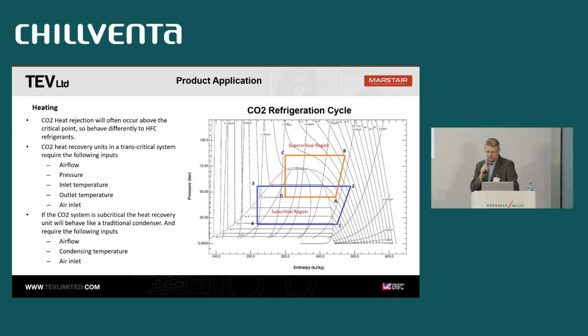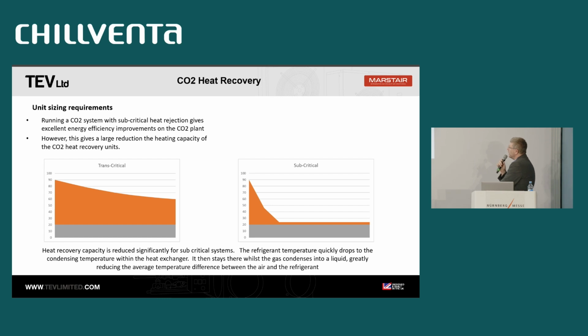Now, the next graph, we'll just go on to the next page. There is a big difference between running the system transcritical and subcritical, so I'll give a little explanation of this graph. At the side, we've got the temperature of the CO2 fluid. This is for heating, and along the x-axis will be time. If you imagine you are the actual CO2 refrigerant traveling through the heat exchanger, when you're transcritical, the refrigerant almost behaves like a chilled water system. The refrigerant starts at a particular temperature and travels through the heat exchanger, and because you've got a higher delta T at the beginning, you get a little bit of a curve as it cools down to your off temperature.